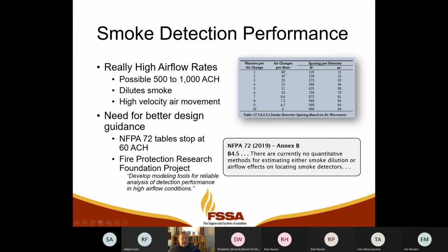We used to use this table. I don't know who's familiar with looking at this, but this table out of NFPA 72 is the smoke detector spacing based on air movement. And so you can look at how many CFM of air is being blown into a space with the air handler, and take the volume and calculate the air changes per hour.